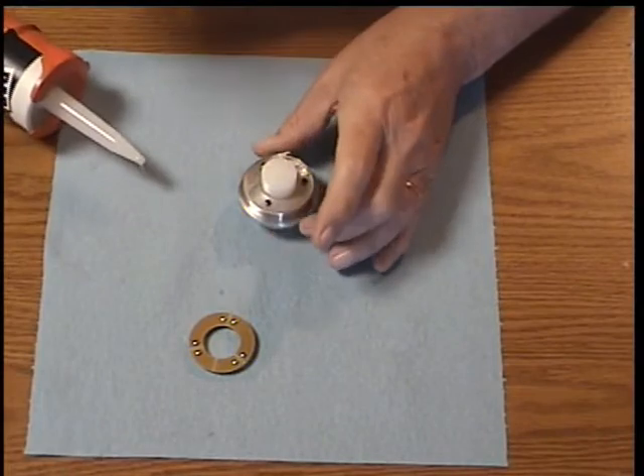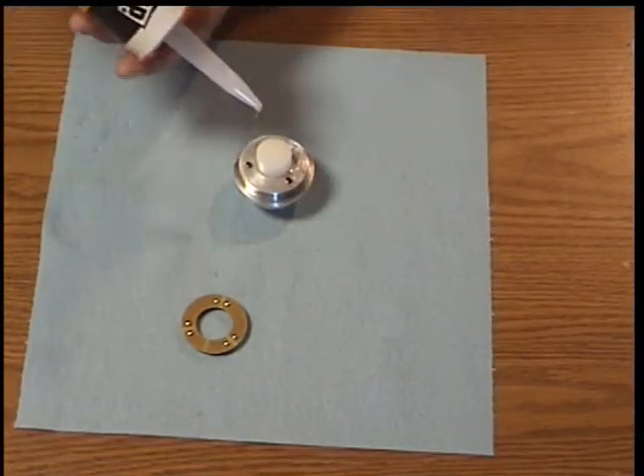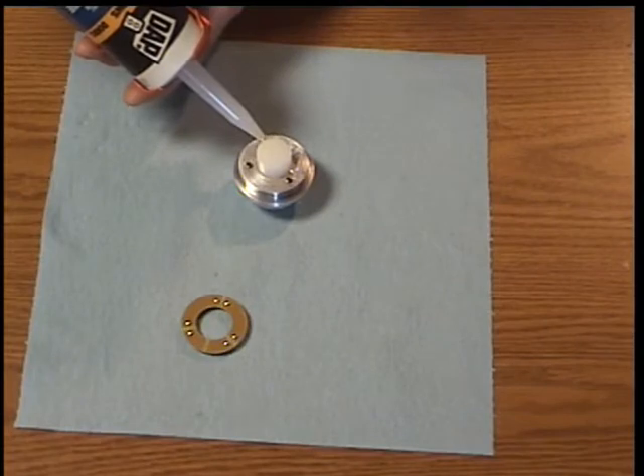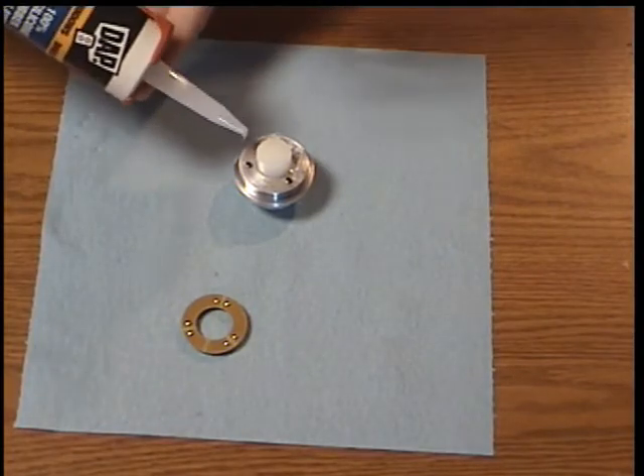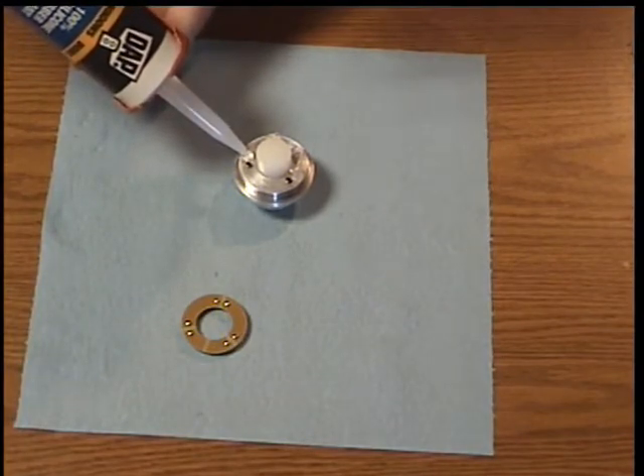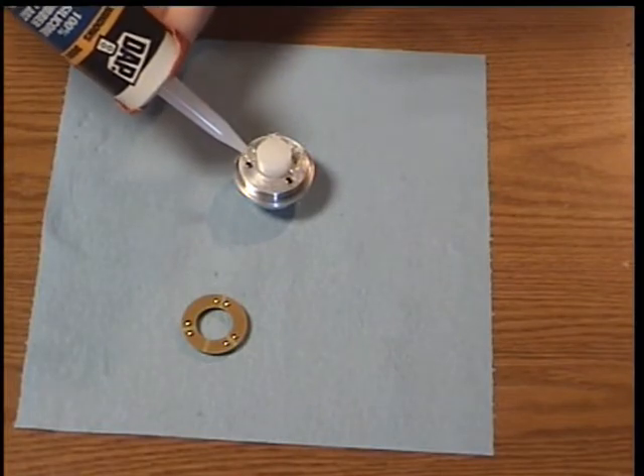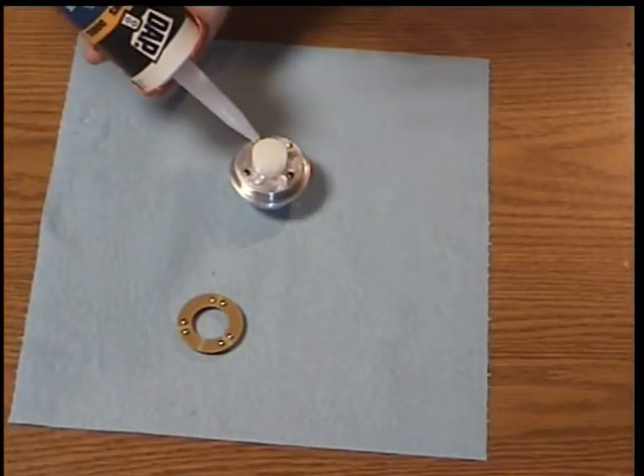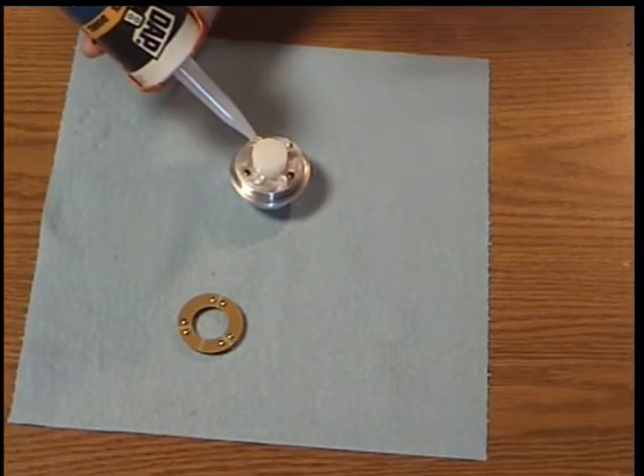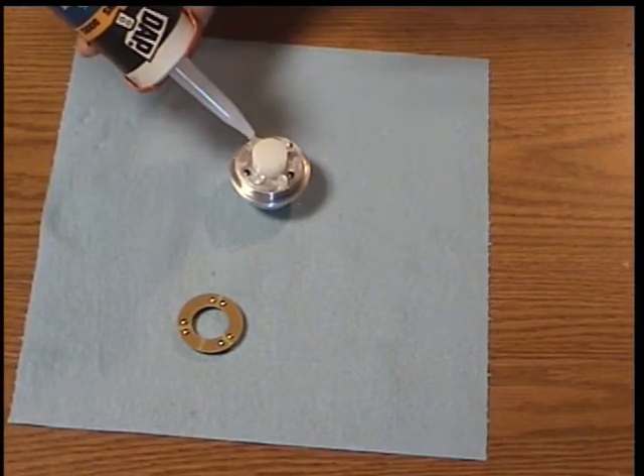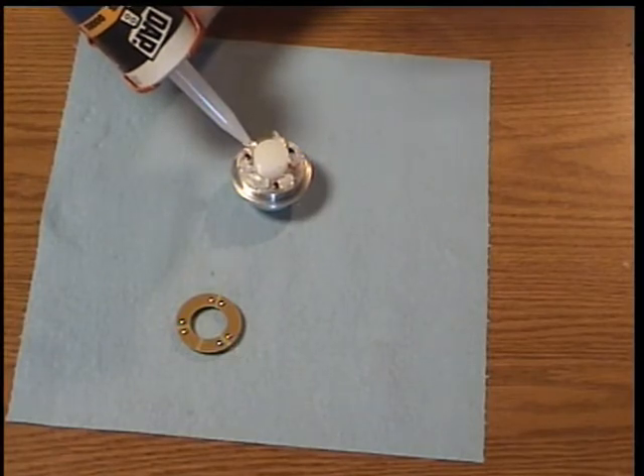We want the adhesive to stick up higher than the set screws. Twice the height that the set screw is protruding is not a problem. Even more than that is not a problem. Try to stay within the confines of the surface that you're applying to, if possible, but if you get a little excess on, it's no big deal. If you get some on the threads from the bottom cap, or even on the set screw threads, it's not going to cause any problem. We just want to be sure that we've got good adhesion between this aluminum surface and the printed circuit board.